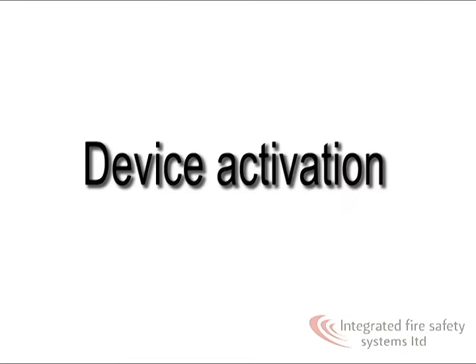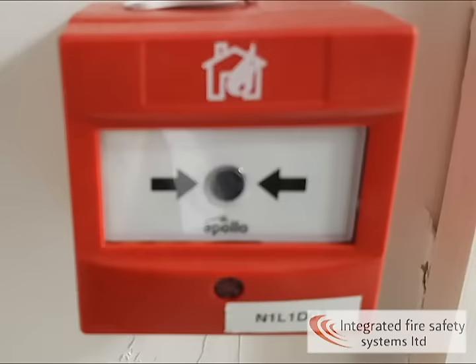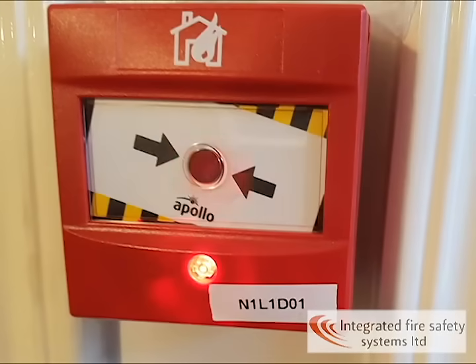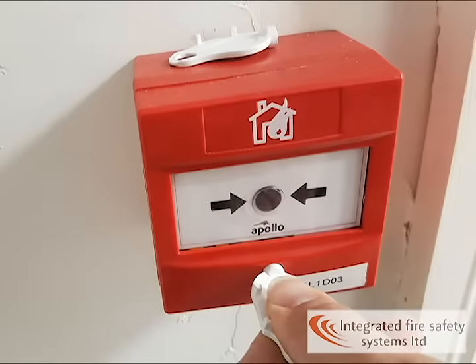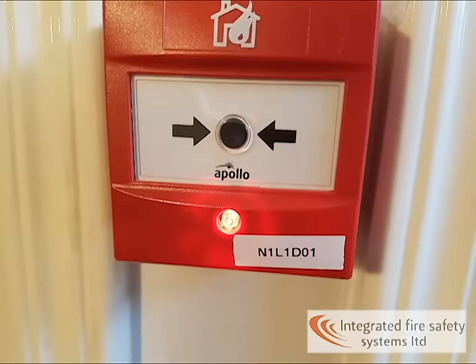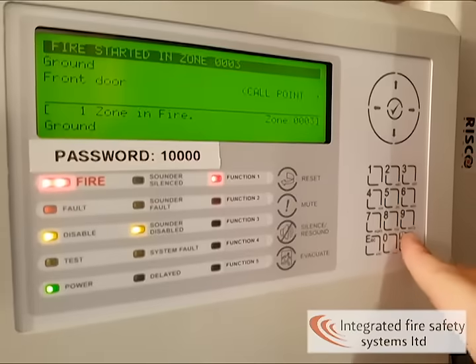We're going to look at some device activations. This is a manual call point. To activate a manual call point, press the glass in the middle of the unit. This will illuminate the red LED on the front and drop the glass. To reset the unit, use the reset key and twist where the LED is shown. This will put the glass back into position and enable you to reset the panel.